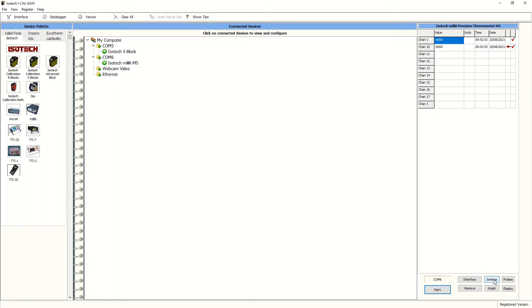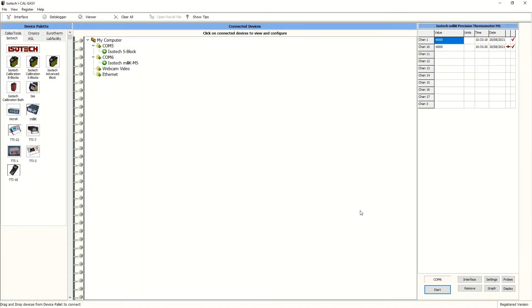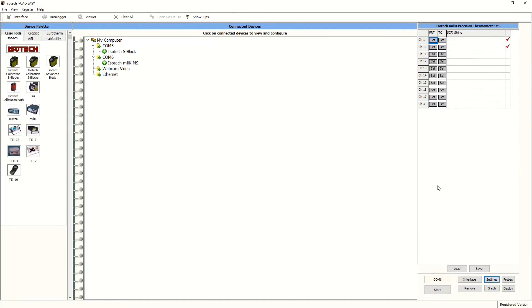So now we need to label each of the positions and activate each channel on the milliscanner. So we can label where the PRT is, the reference and the thermocouples using the settings tab.